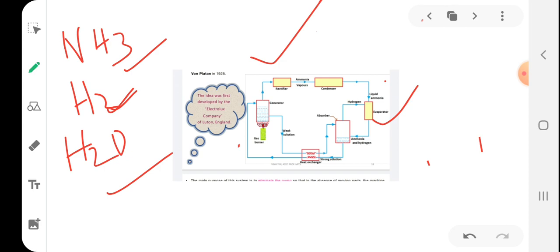So the hot weak solution is left behind in the generator. After heating, the ammonia vapor enters the rectifier, and some weak solution is left in the generator. What happens to that weak solution? This hot weak solution will pass through the heat exchanger, right? While passing through the heat exchanger, what will happen? It gets cooled. Why?